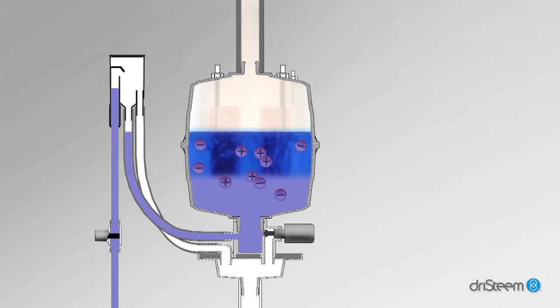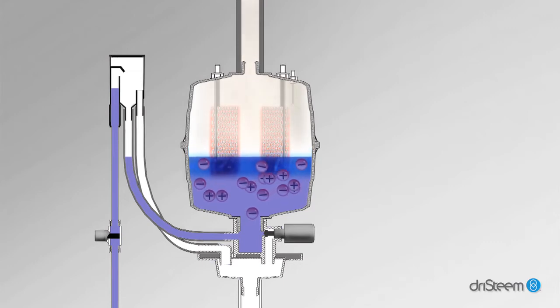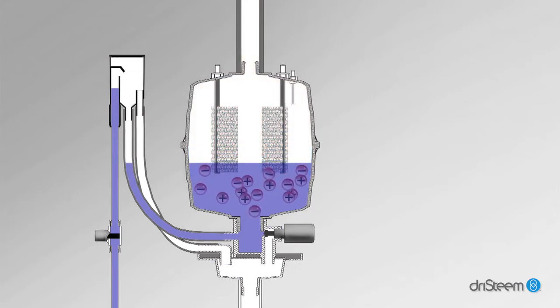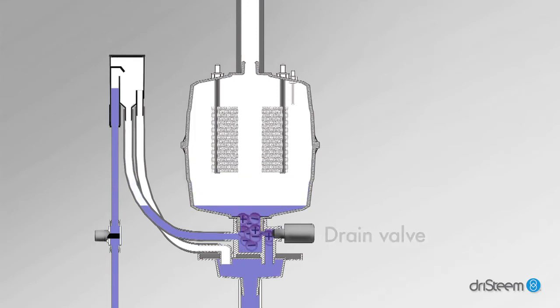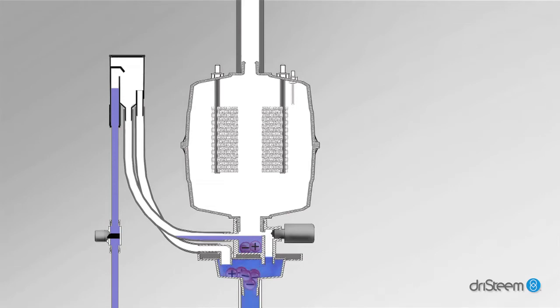As water boils away, the concentration of conductive ions in the water increases, which increases electrical current through the water. At some point, the controller must reduce water conductivity by opening the drain valve and flushing the overly conductive water, then replacing it with fresh fill water.